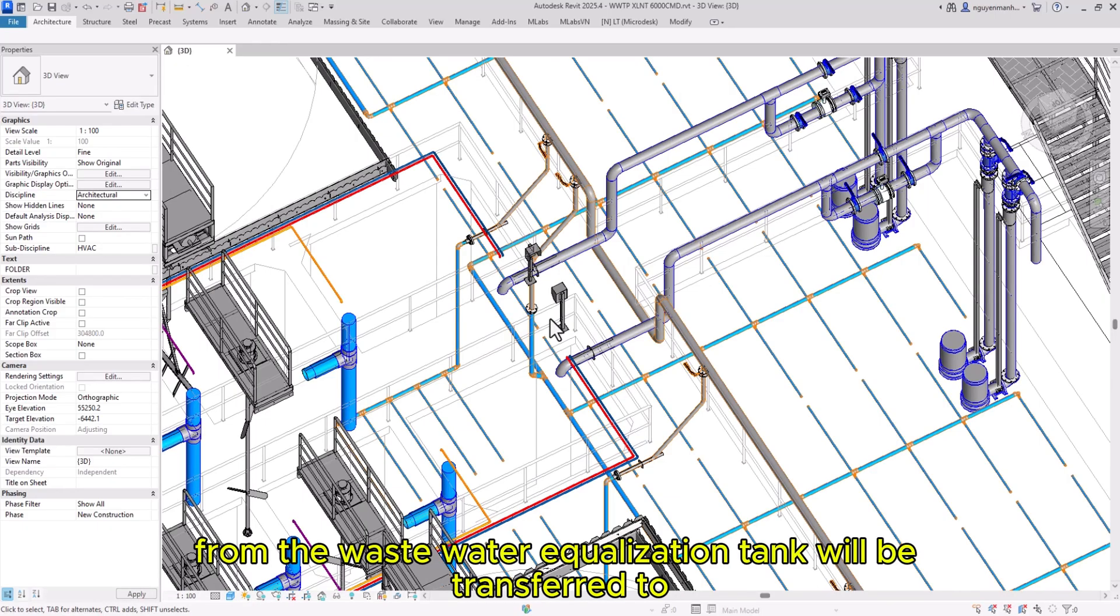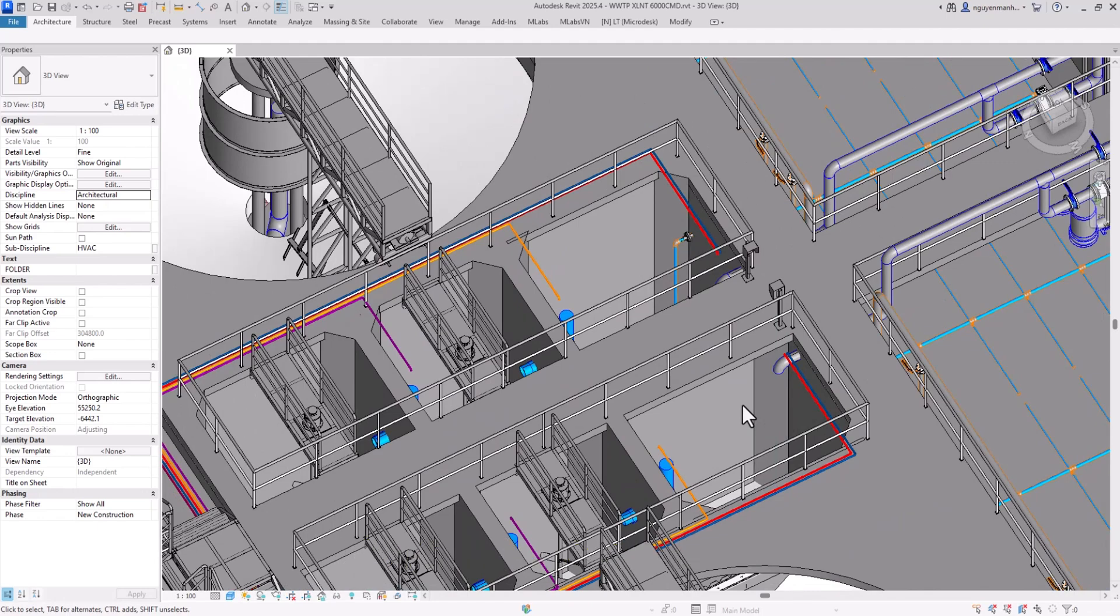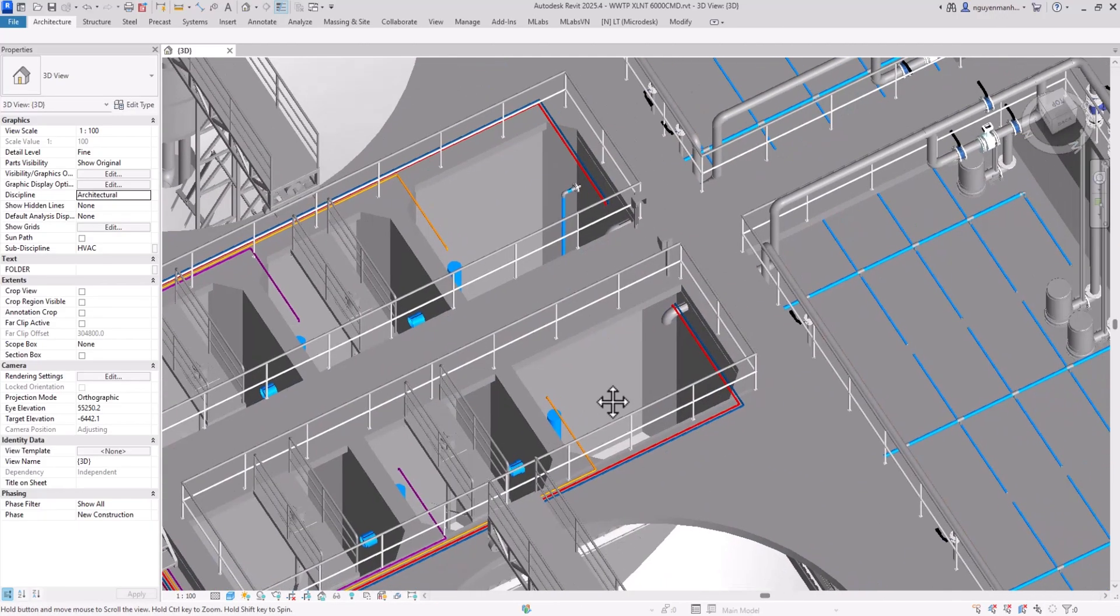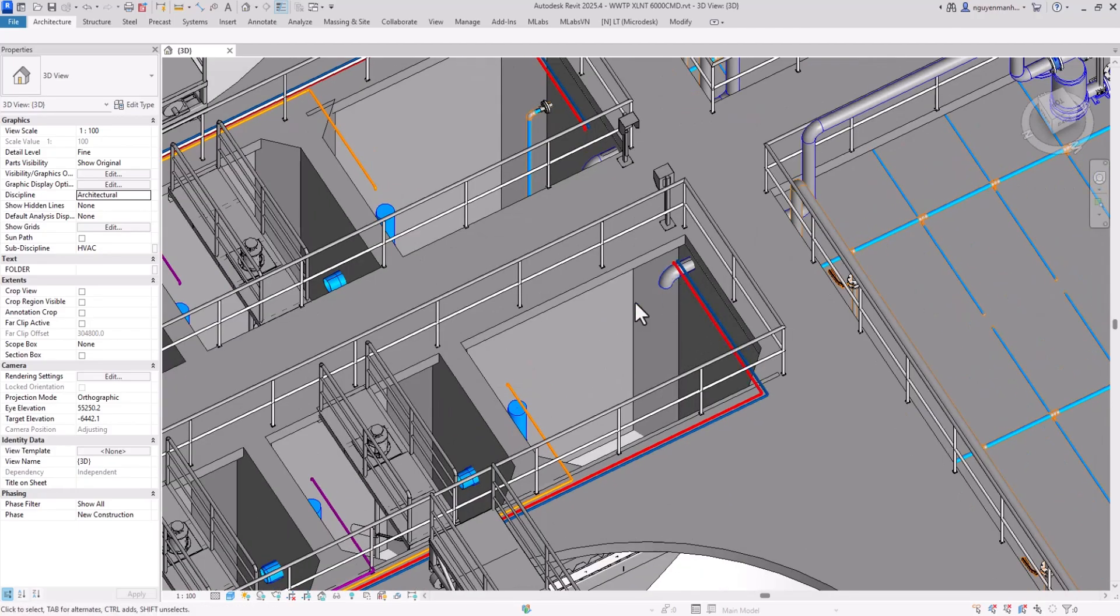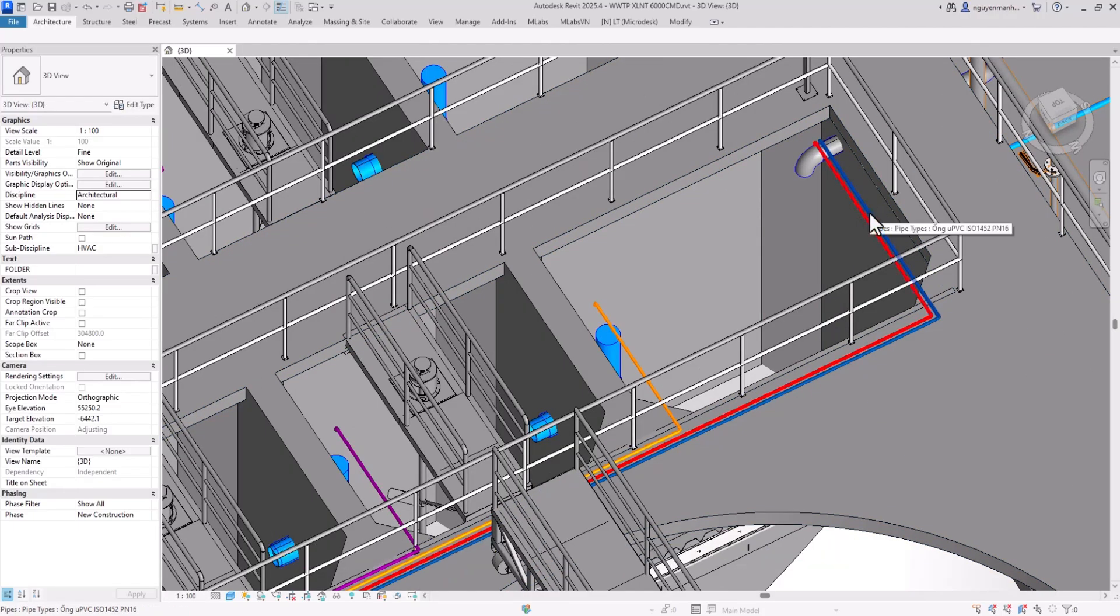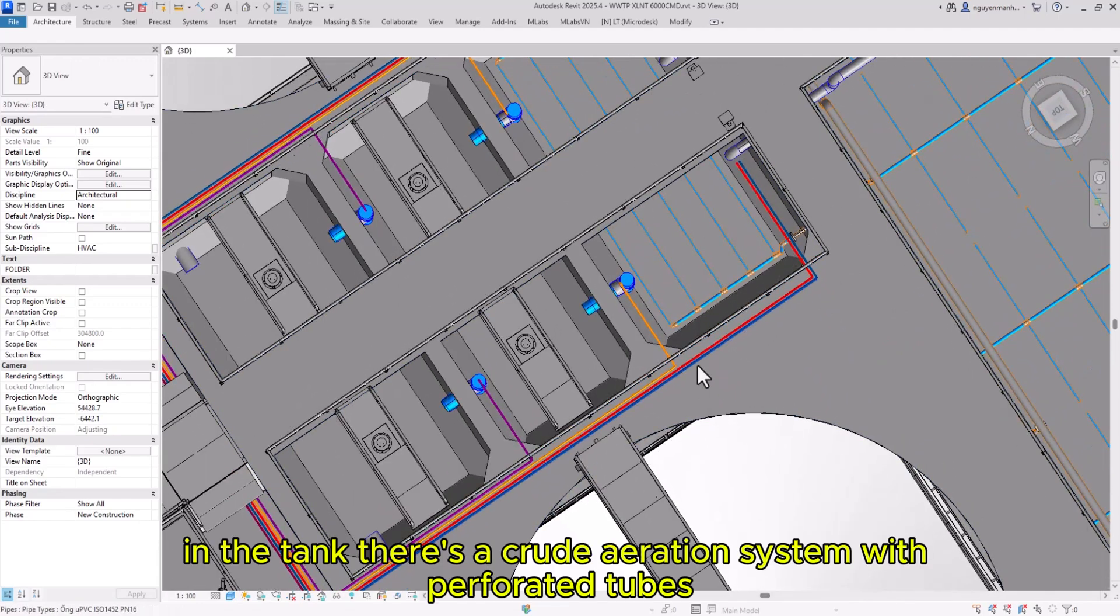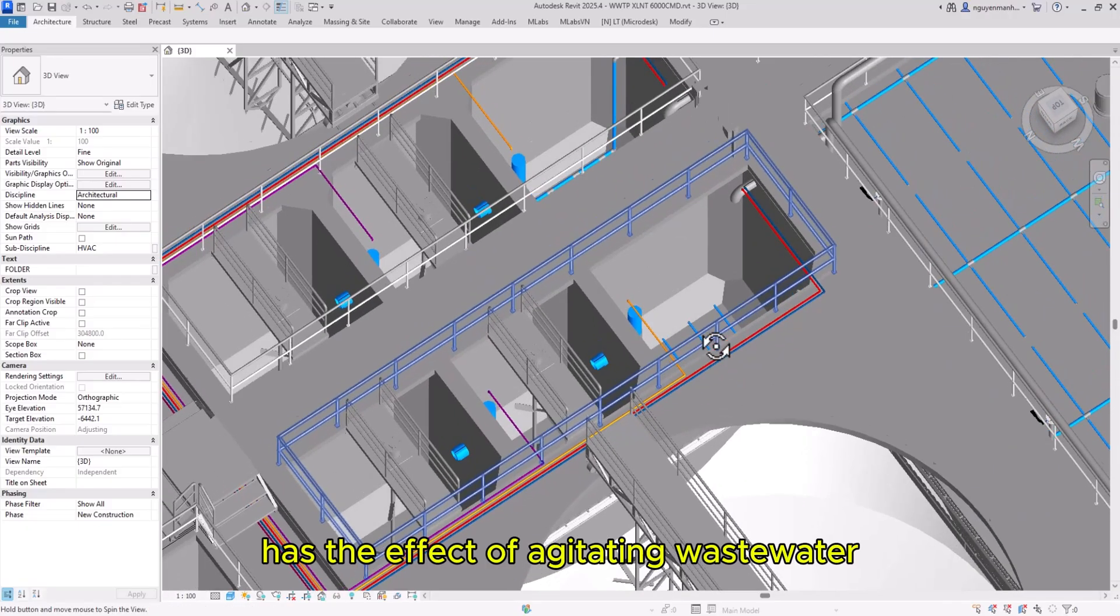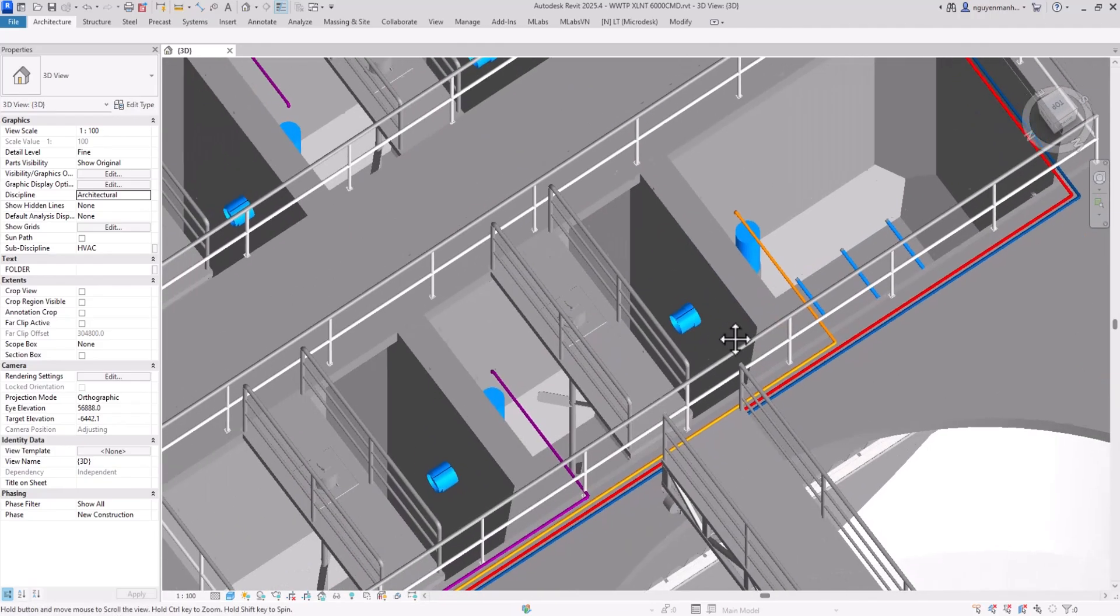From the wastewater equalization tank, water flows to the pH adjustment tank, which has pH measuring equipment. In this tank, we use two chemicals: NaOH and acid H2SO4. A pH adjustment device controls the process. The tank also has an aeration system with perforated tubes that agitates the wastewater. The wastewater then overflows to the flocculation tank.